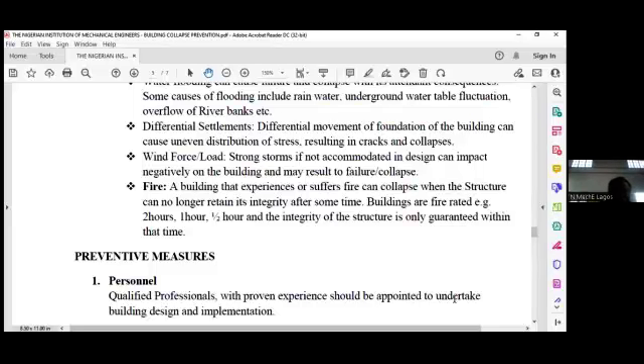There are other things too, like lightning protection. The engineer designs for when thunder strikes and conducts heavy currents, in kiloamps, safely and slowly into the earth without damaging the building. There's also bonding of all metallic elements and equal potential bonding around the building so that human beings are not affected.